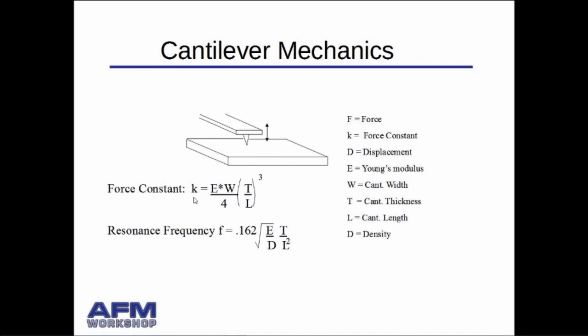And so the parameters that establish the force constant have to do with the Young's modulus, the width of the cantilever, and the thickness over the length to the cube power. So it's very dependent on the thickness and the length of the cantilever. So if the length gets longer, the force constant goes down very rapidly. The resonant frequency, again, depends on these parameters, and so these things can be calculated based on the materials that you have.